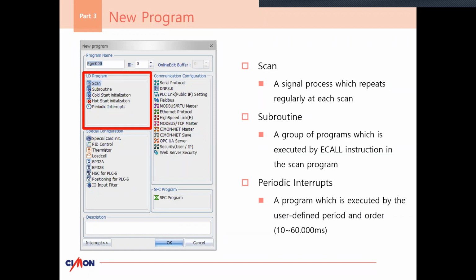Some people might know about subroutines, like being able to jump onto another scan in the middle of a program and then come back to the original scan to keep going with that logic. So in our logic, that's called a subroutine. You wouldn't want to use a scan to try to target another scan - that won't work. When you use the subroutine, you'll use an eCall instruction, which will target that other scan, and then it will come back to the normal scan after it's done. That's a familiar trait from other competitors, but ours is called subroutine.